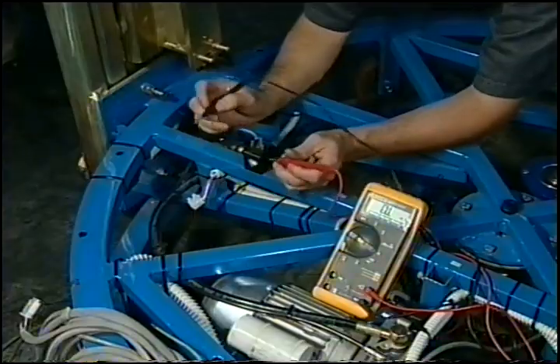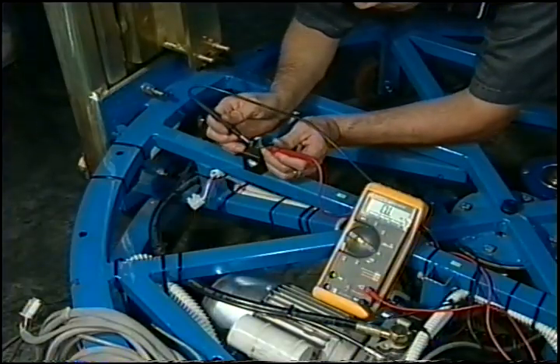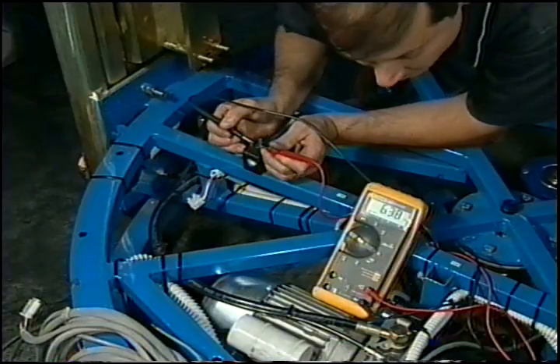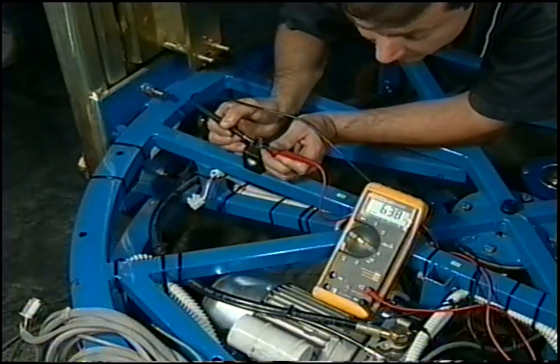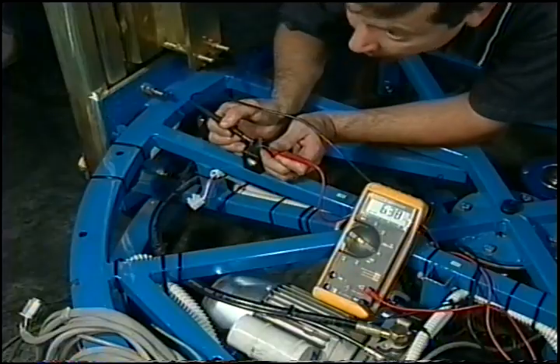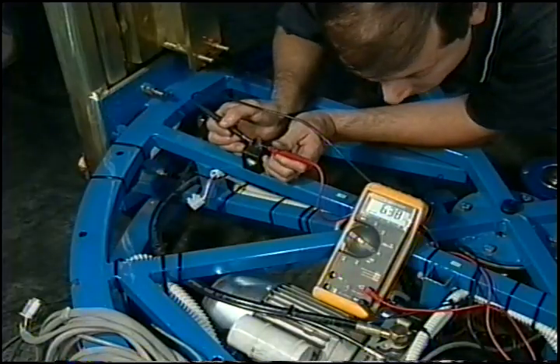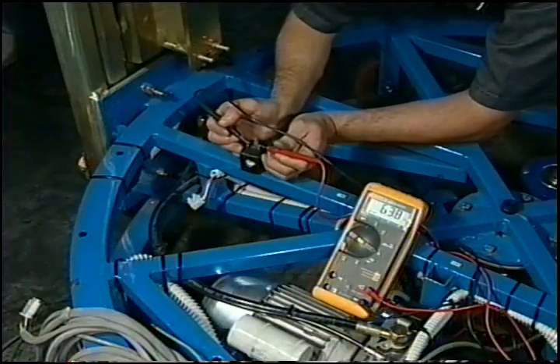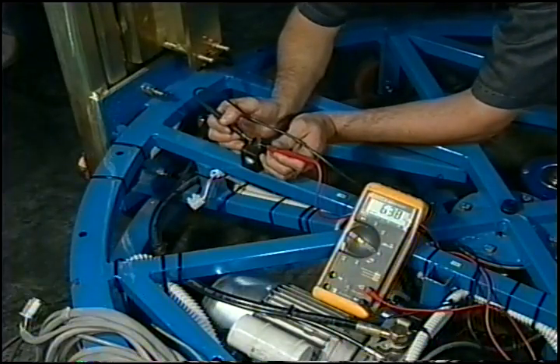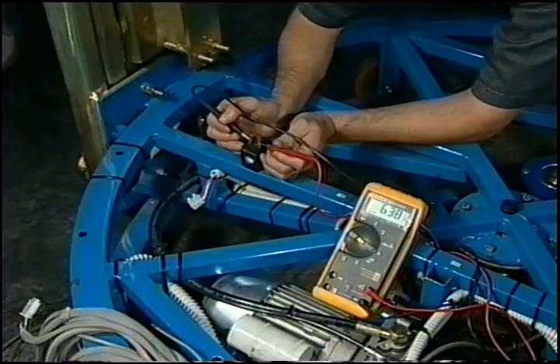To check it, you just take each of your meter leads and go across the two pins. When you do so, you're going to read anywhere from 360 ohms to 640 ohms. This one here reads 638 ohms. Generally, when they go bad, you read infinite resistance, almost an open circuit.